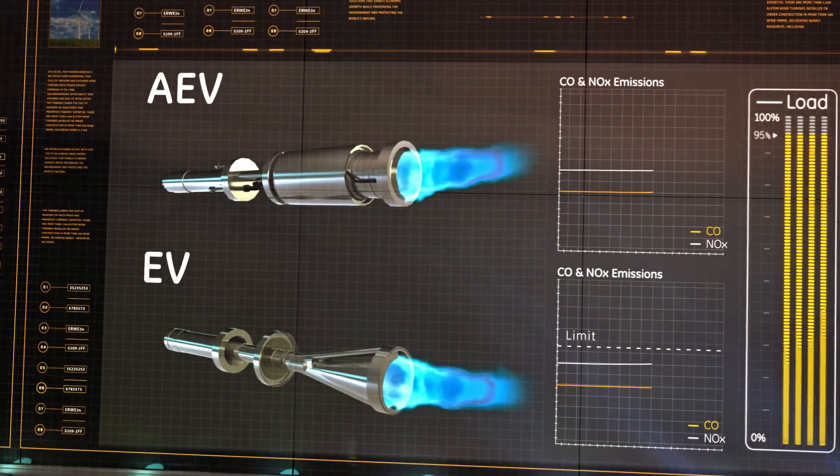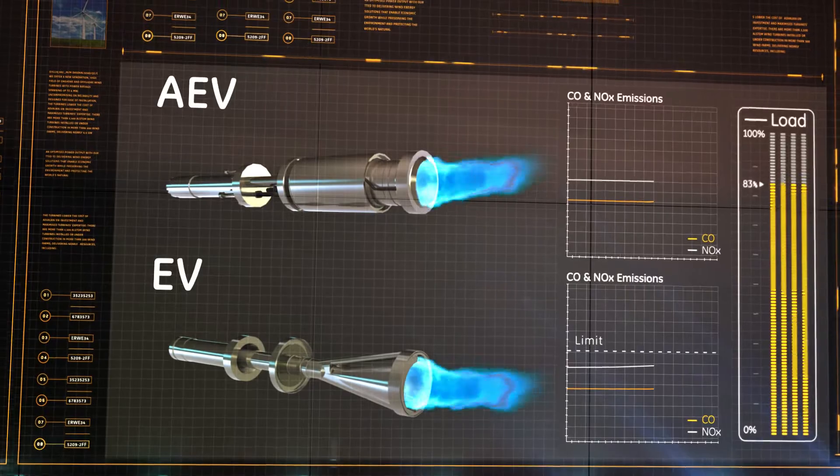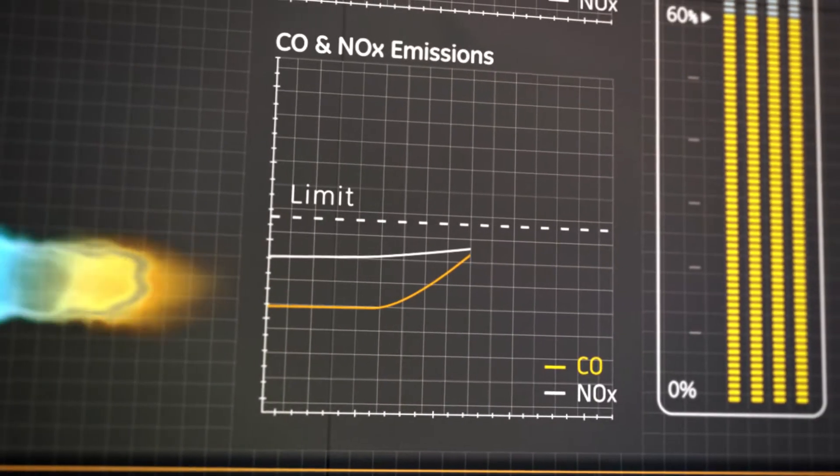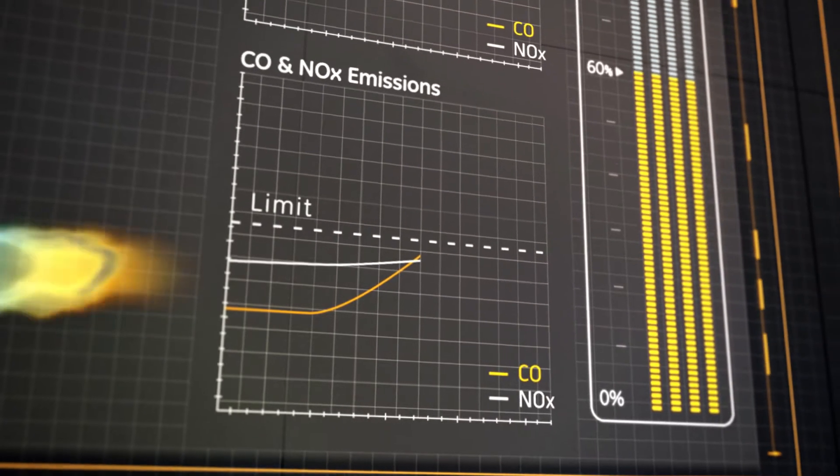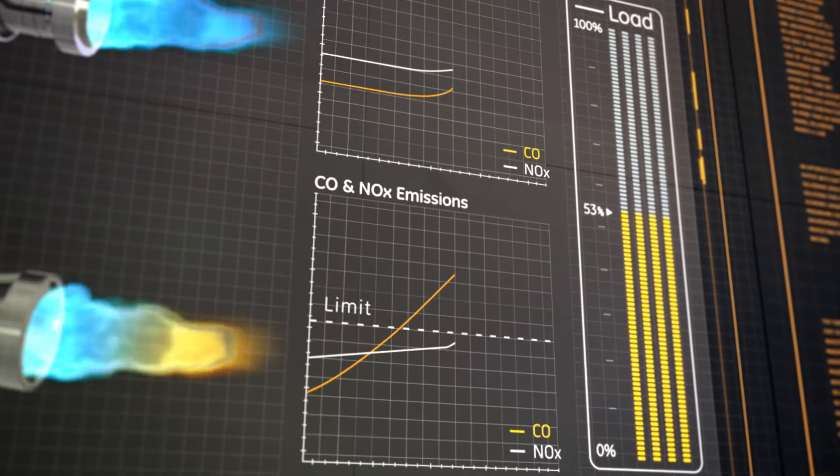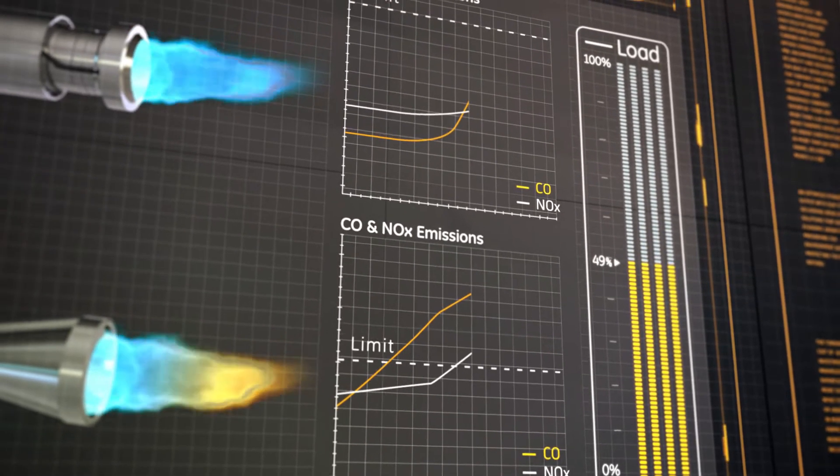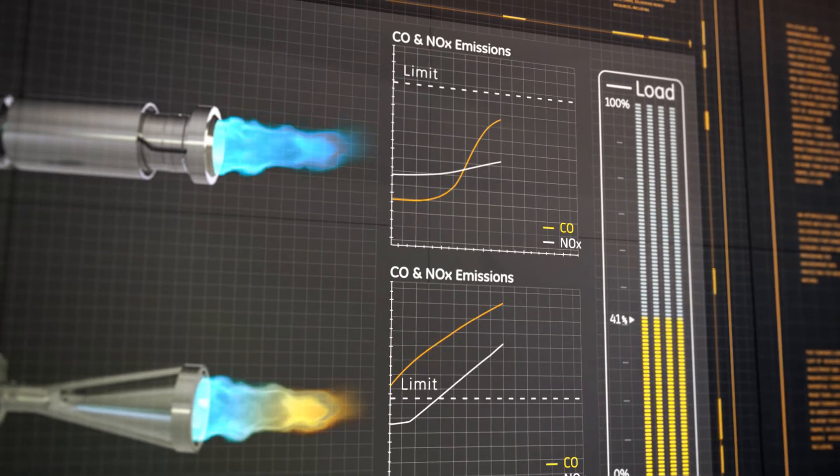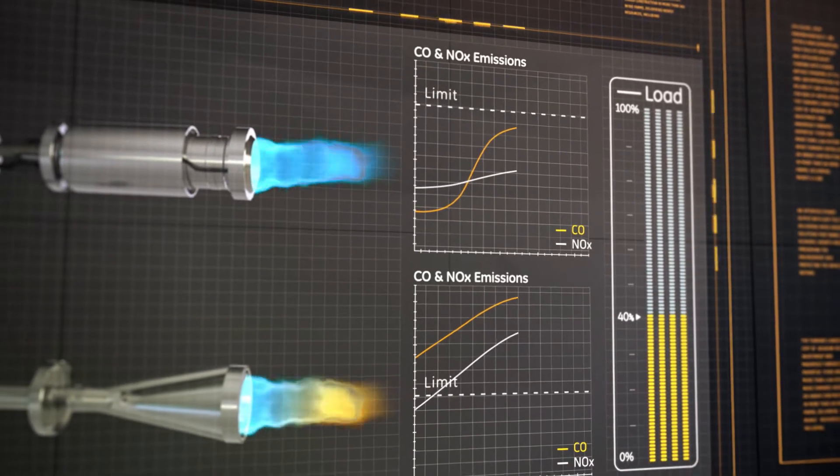As power output is reduced, the EV burner typically switches back to pilot operation at 60% GT load, resulting in a step increase in emissions. The AEV burner's innovative concept of continuous fuel staging eliminates a switch over and switch back, allowing emission-compliant GT operation down to as low as 40% GT relative load.